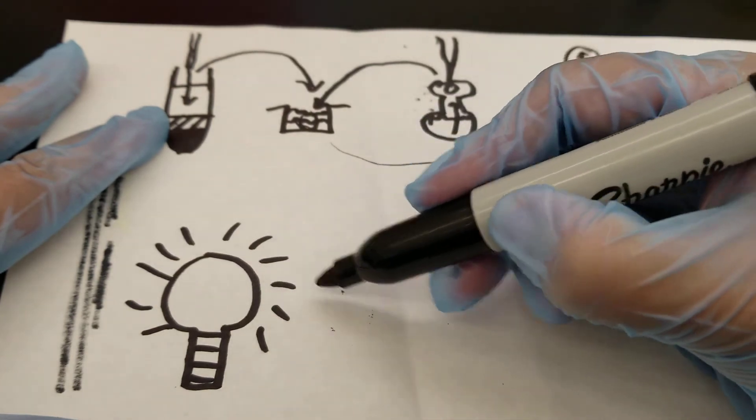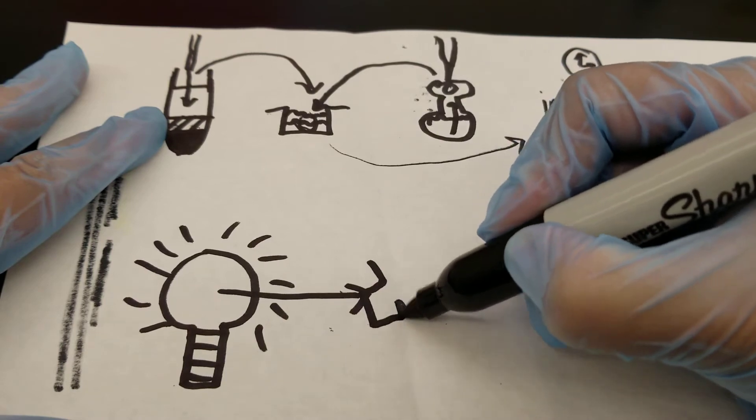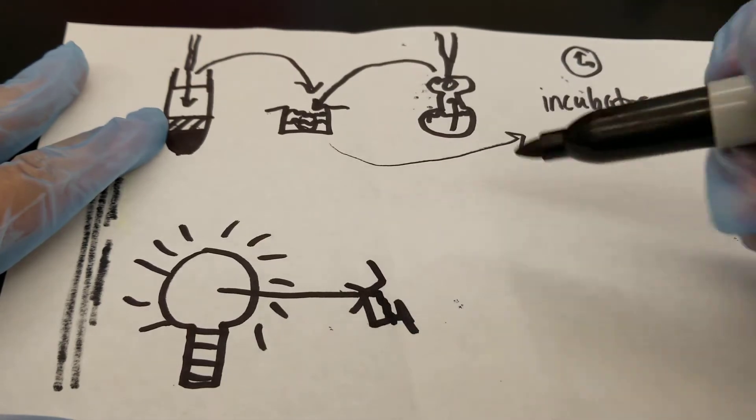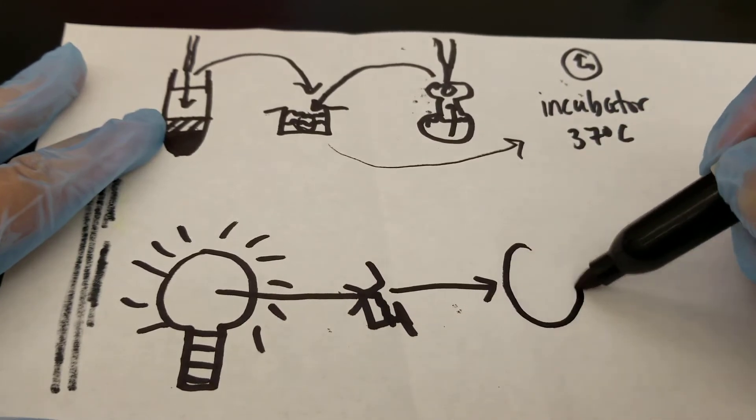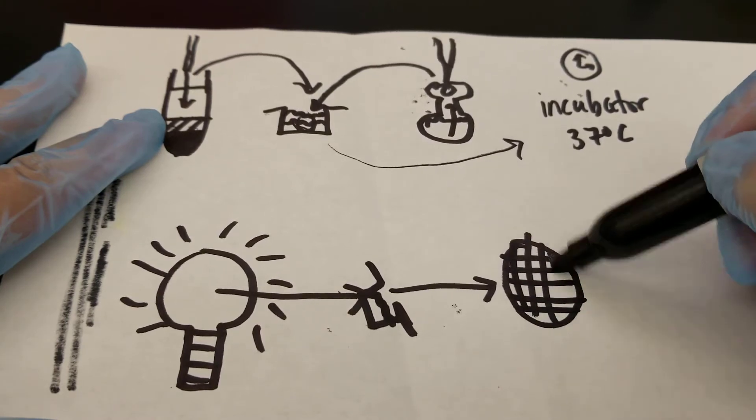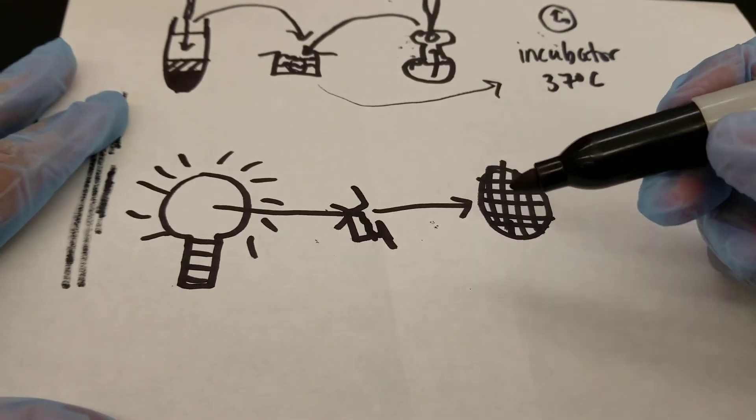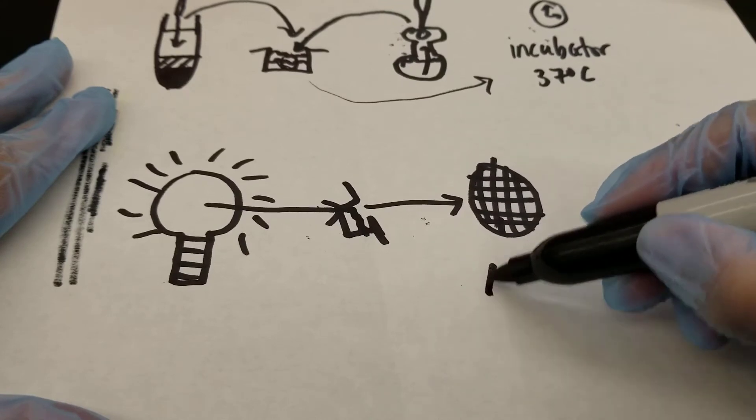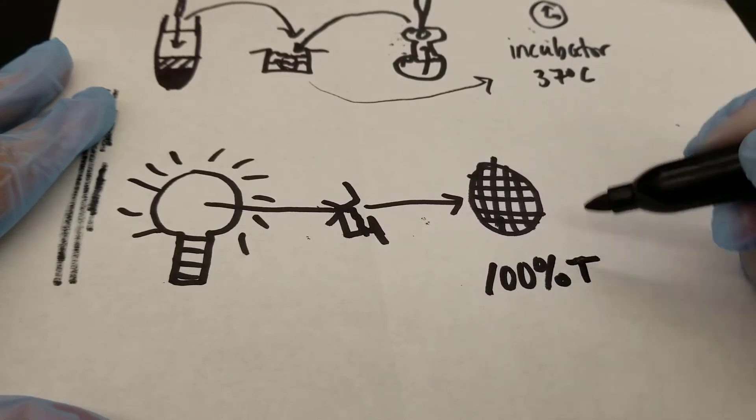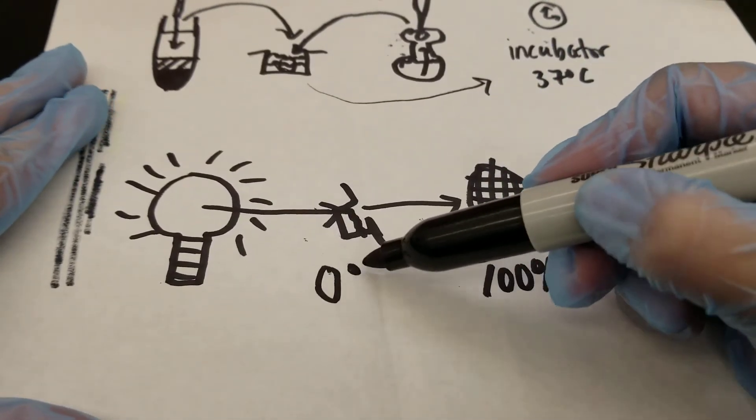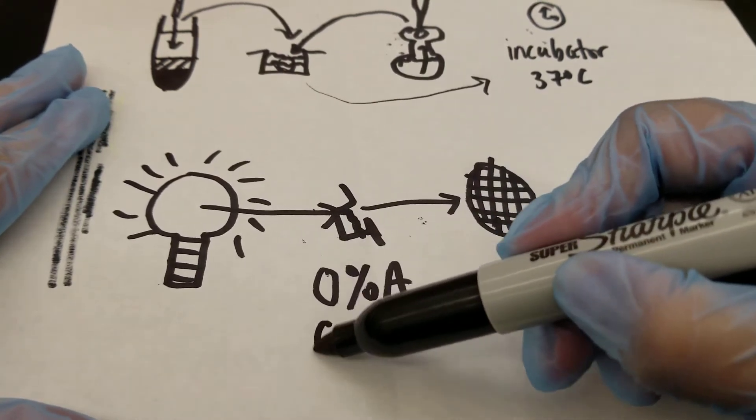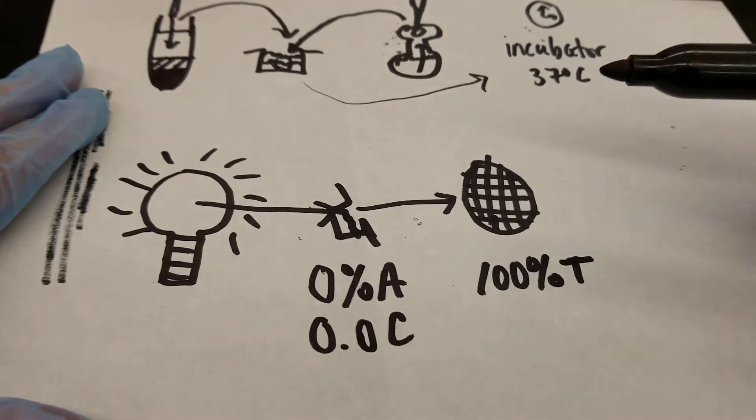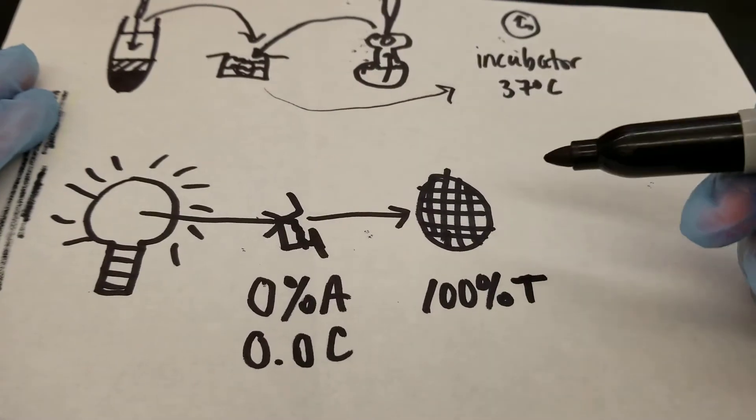The light ends up getting shined through the cuvette that has that mixture in it. And it goes and it gets read by a sensor. Now, what we end up looking for is transmittance and absorbance. So if there's 100% transmittance, that means 100% of the light went through. And then that would then equal 0% absorbance. It would also be zero concentration of whatever it was that you were looking for.